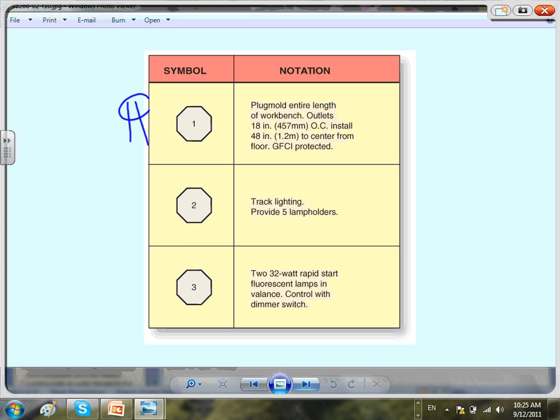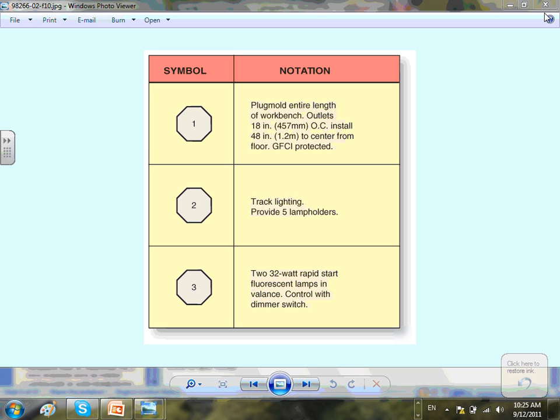When you guys design the project, you come to your friend Chad, and I'll be asking, how do I know that this receptacle is an arc fault circuit interrupter or protected? You want to come to me. Everything has to be arc fault circuit interrupters. How do I know? You have nothing on your plans that tells me that, so it's a good note to say arc fault circuit interrupters.